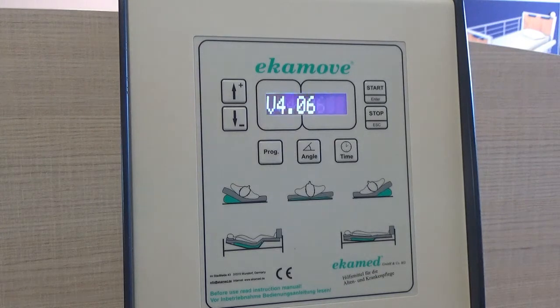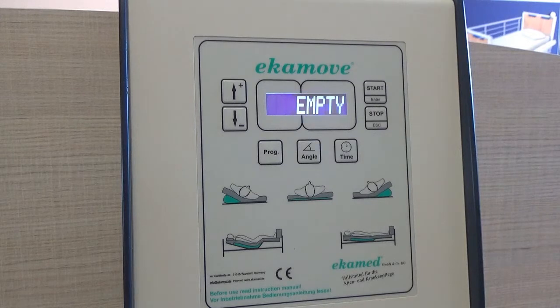The Ekamove should be plugged in at the mains and then turned on using the switch under the control unit. You will see the software version number and the percentage of memory capacity left on the memory card rolling across the screen. The word empty then runs across the screen and the system will automatically withdraw all air from the air chambers and calibrate the sensors. Calibration takes approximately 5 minutes, but it is important to complete the process.